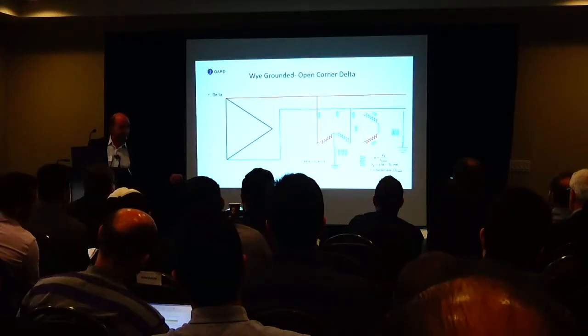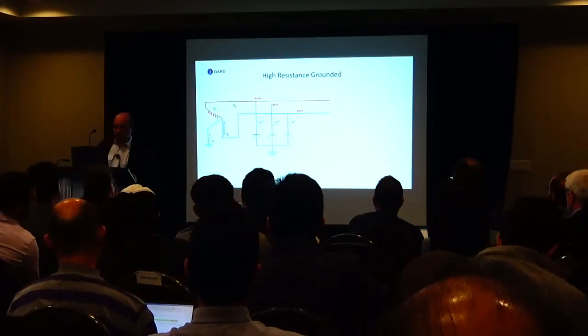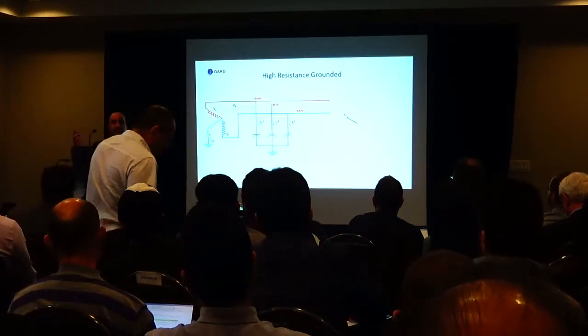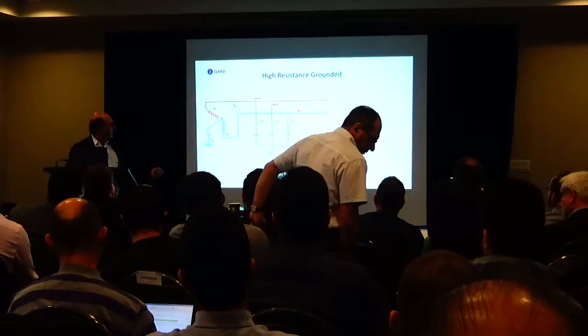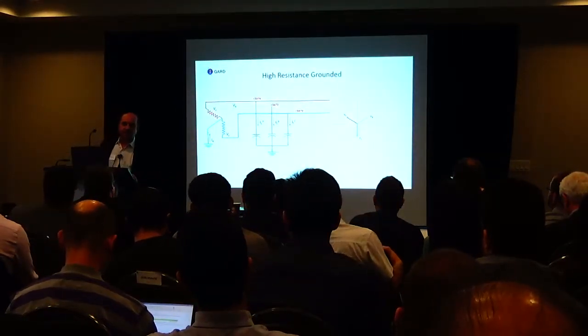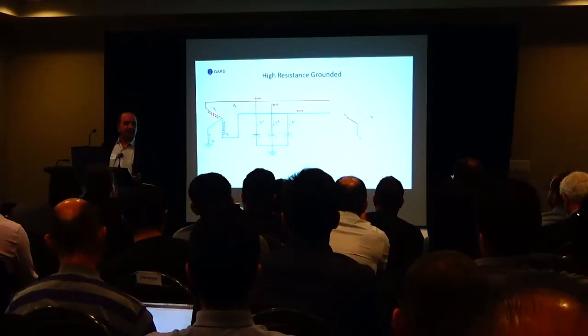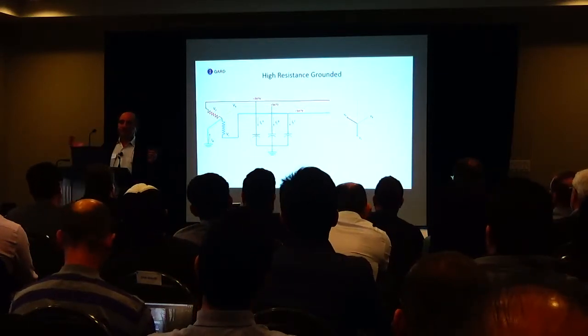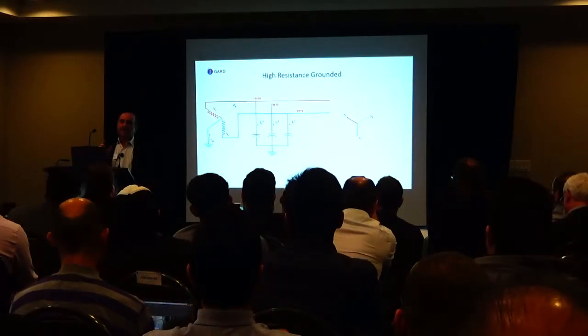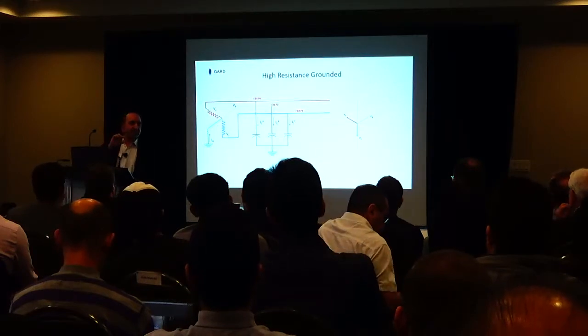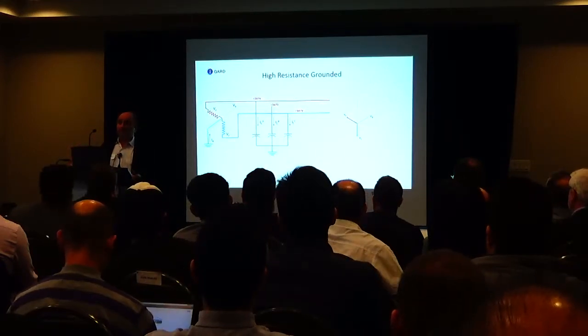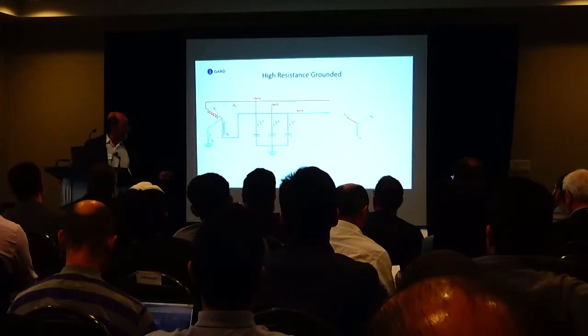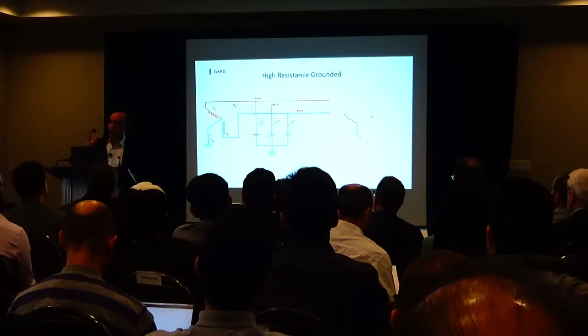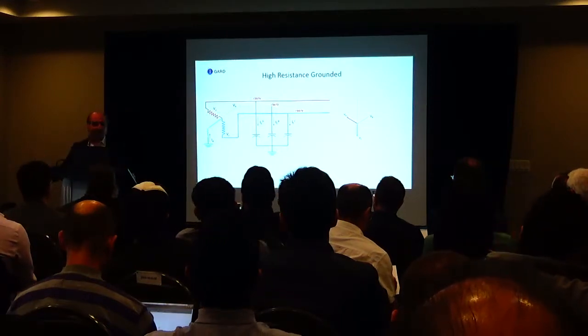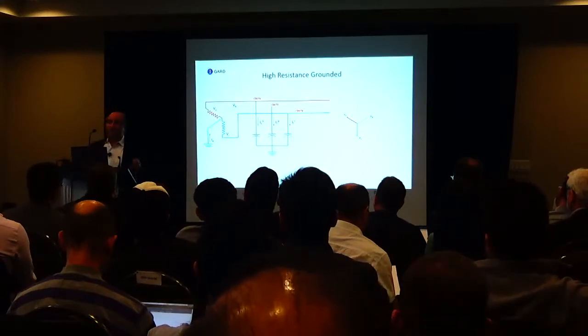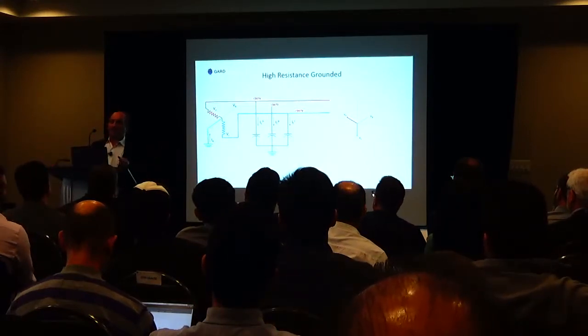And all the values here you can use, and they're on our application guides as well. So Sergio was talking about the capacitive curve. When you have a normal system, you have capacitance. Think of your cables as capacitors, because you have two potentials isolated from each other by an insulated medium, and an insulated medium is the insulation on your cable, or air. If you have a bus duct, air is an insulated medium. That's a capacitor, but that capacitor is distributed throughout the entire length of your cables, your busways, and everything. So what I've done here is I've drawn the capacitors not as a distributed capacitance, but as a lumped capacitor.